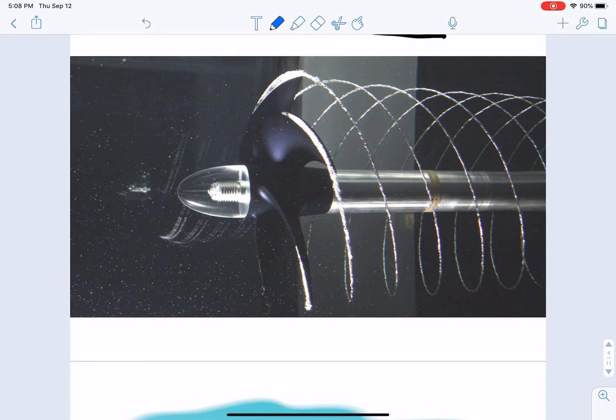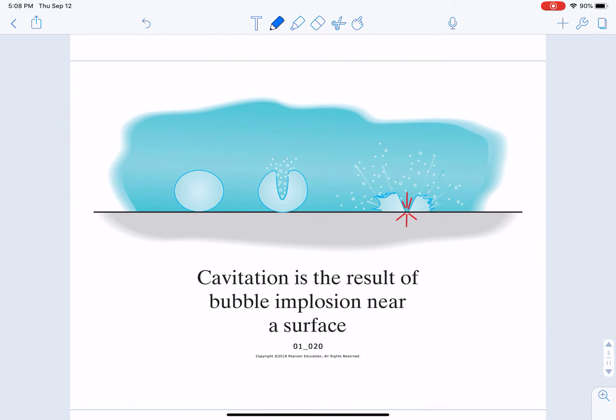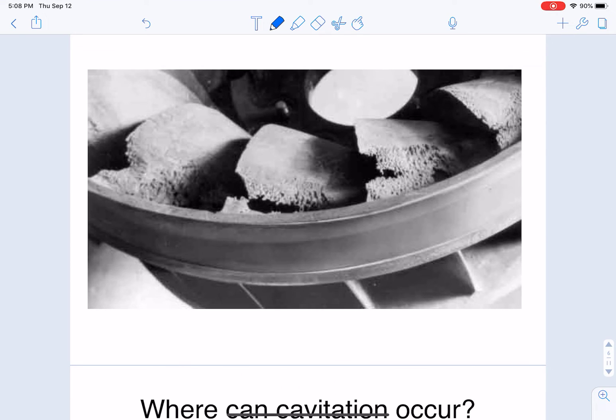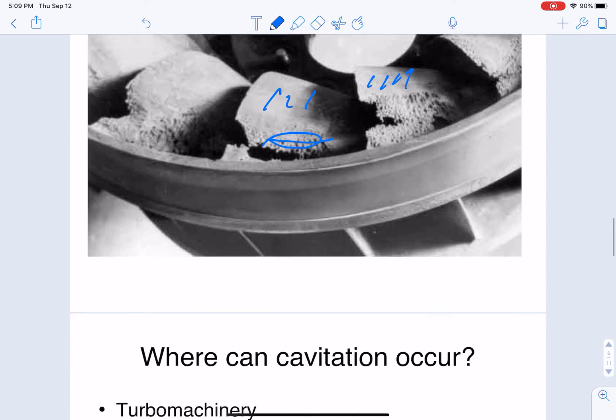Cavitation occurs when vapor pockets form at a really low pressure spot in the system where the liquid pressure matches the vapor pressure. Those vapor pockets are transported by the liquid, and technically cavitation is the process of those vapor pockets hitting a solid surface, collapsing, and releasing a ton of energy — which erodes away the solid surface. Looking at a pump impeller over time, this solid metal alloy is being destroyed by cavitation bubbles hammering away at it.